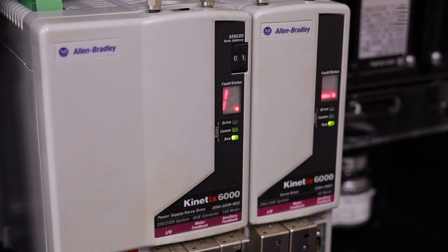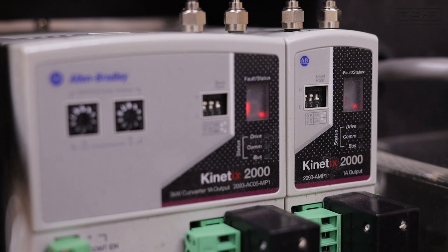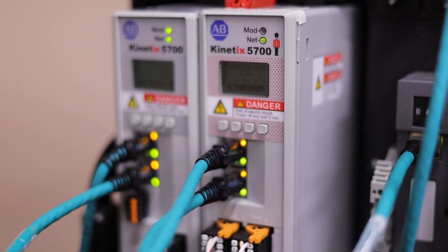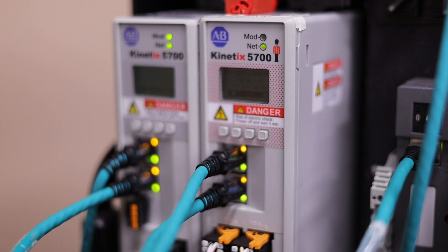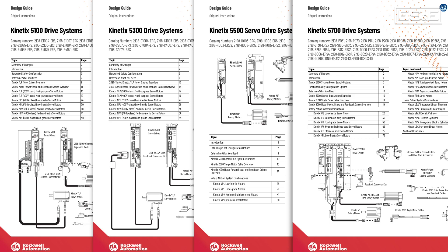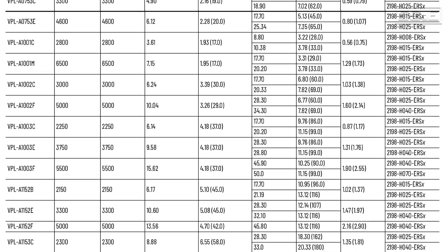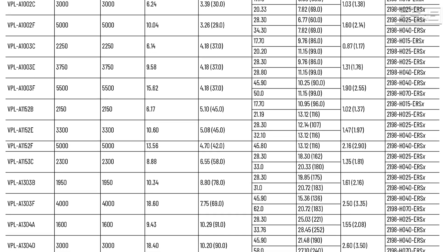Step 1: Convert the hardware. Let's start with the servo drive. You'll need to find the Ethernet IP servo drive that corresponds to your current SERCOS servo drive. Rockwell's Kinetix 5000 series servo drives all use Ethernet IP for communications and control. The 5000 series drives are the newest available. It's a simple matter to size the correct drive based on the current servo motor being used. In the description below, there are links to the design guides for each of the 5000 series servo drives. These design guides contain lists of all the compatible servo motors for each drive family, and also provide a recommended drive based on a given servo motor.